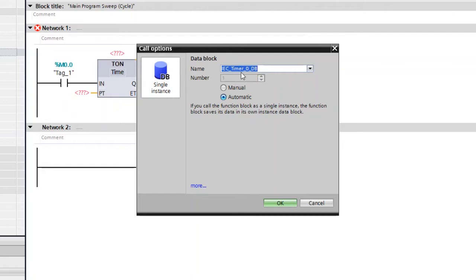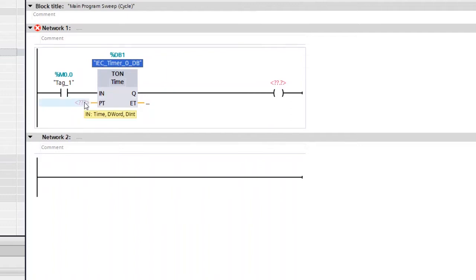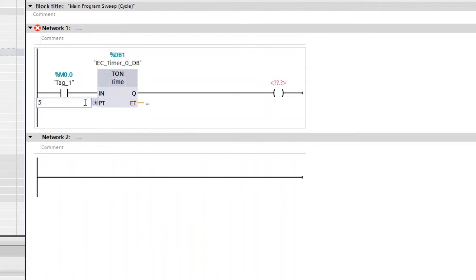Here you can see the call options. Go ahead with the default name IEC Timer 0, set to automatic, then click OK. Now you can see the address has been assigned using IN and OUT. PT is the preset time — we need to assign the time. I would like to give a five-second delay, so type 5 and S, then Enter. Now you can see the preset time is set to five seconds.